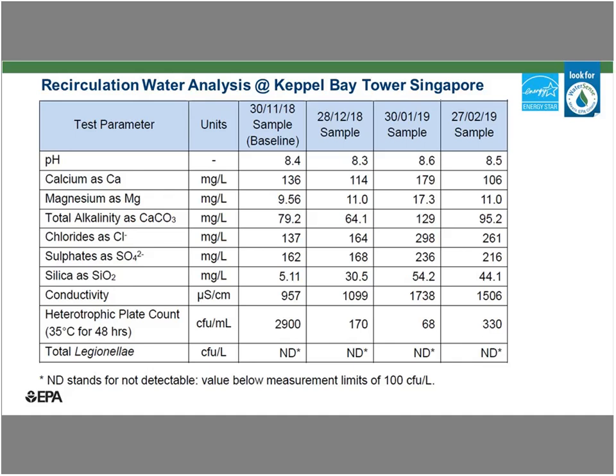You will notice that the conductivity is higher, but like I said, we are running such high COC that other minerals are contributing to this conductivity reading. Of course, the bacterial count as well, we need to meet the standards. They were getting a 4-digit count, we are getting 2- and 3-digit counts for bacteria. For Legionella bacteria, it's not detected, so we also show non-detection of Legionella.